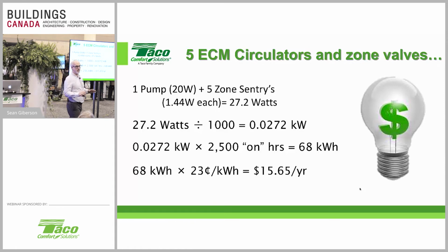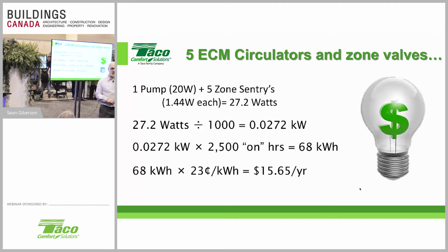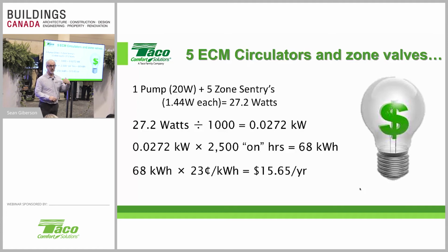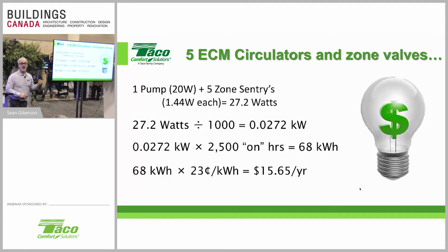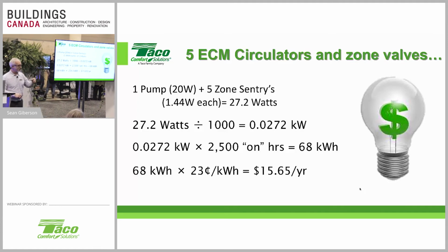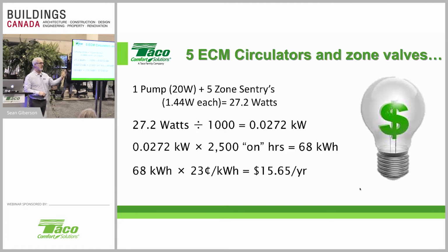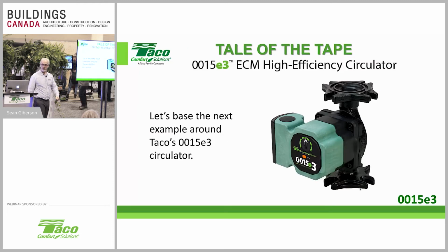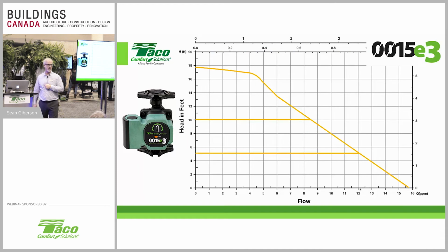We didn't even talk about the impact on the boiler, because remember, if we start to play on the pump curves and figure out how the system curve intersects that, there's going to be impact on those boilers and the performance aspect of that. So now you bring a gas bill or whatever other energy piece you're doing into play. So let's just talk kind of the tale of the tape, and I'll build this around this 0015e3. This is a circulator that's a three-setting circulator, okay?